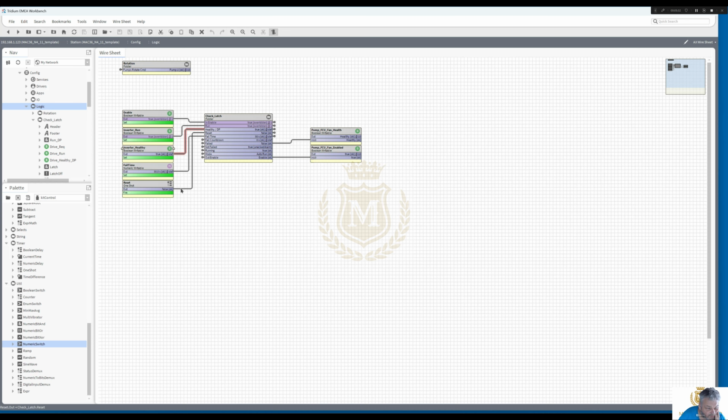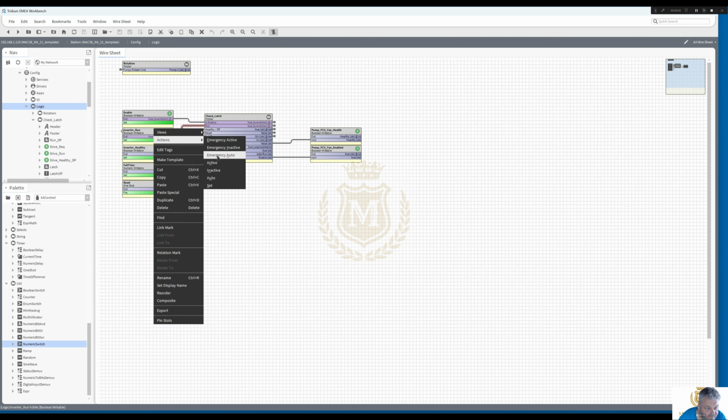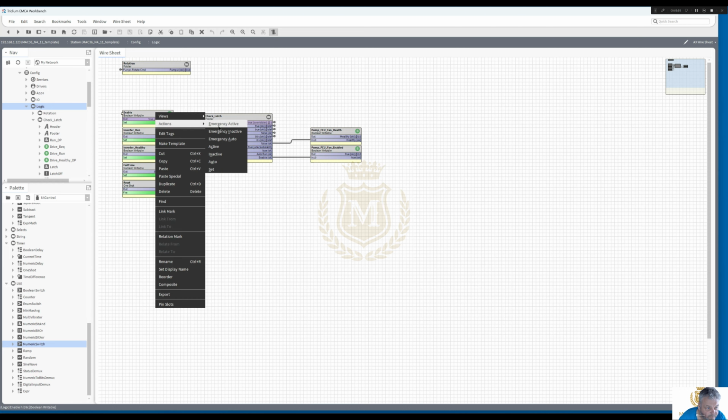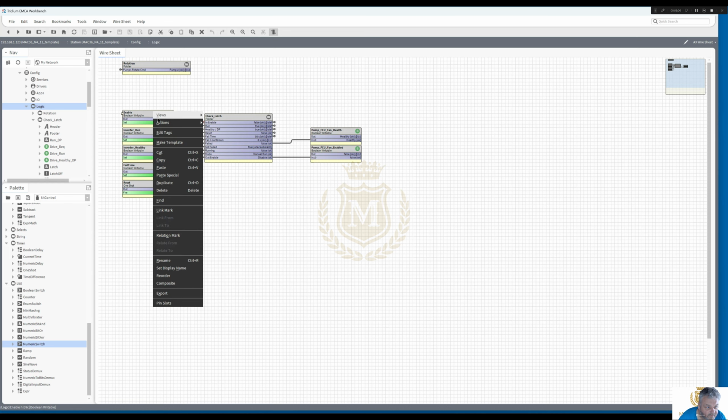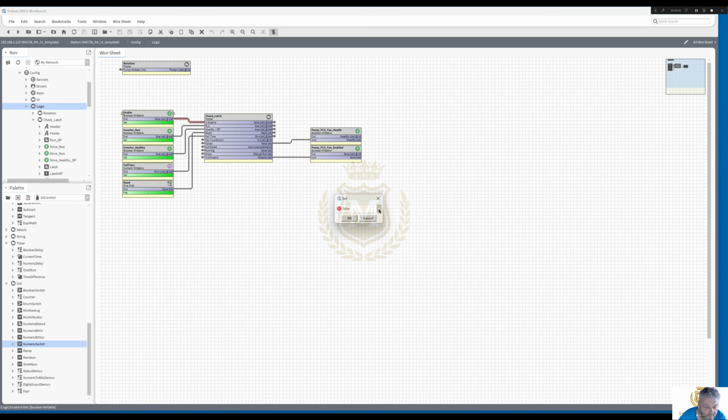So when we go into fault, we can't restart that pump, that fan coil unit, extract fan, supply fan, whatever you want to call it, until we've reset the system. It must have a reset. So we're latching the fault, and it will not start again until the reset has been completed. Let me just take all these back to auto. So that's back to false, disabled. Let's set that just to true, and we can then look at the logic.